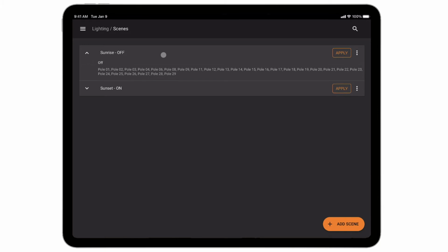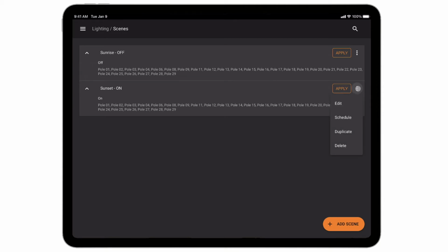And if I click on one of the existing scenes, I'm going to see some more details about the behavior that's assigned to those scenes and then all of the zones. This site, every single pole is its own zone, and there's an occupancy sensor on both of the lights. So if either of those occupancy sensors detect occupancy, it's going to turn that pole on, if we're using an occupancy behavior. At the moment, we're not. So that's what we're going to go set up. We're going to go over here to the three vertical dots on the right, and we're going to click duplicate.